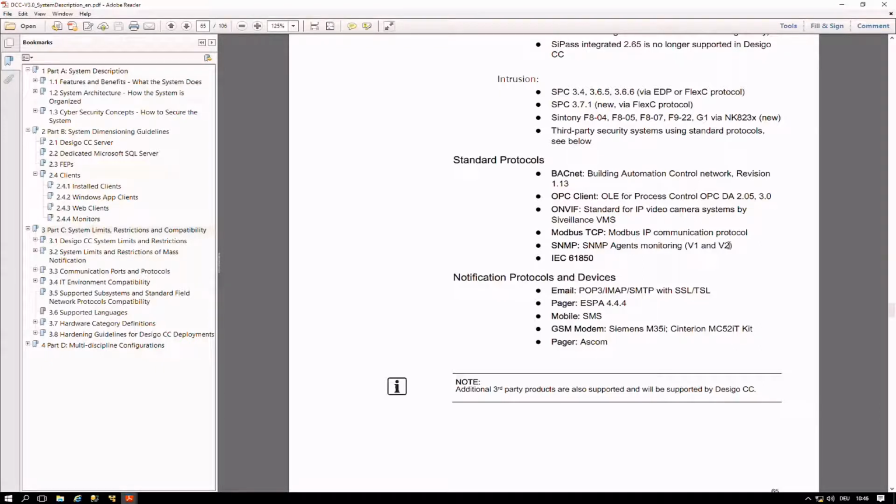Okay, so those are sorted out with service release 6 of version 2.1, and now with version 3. You don't have these issues anymore. And obviously, if you're having more than 254 devices, you need to configure one more driver.